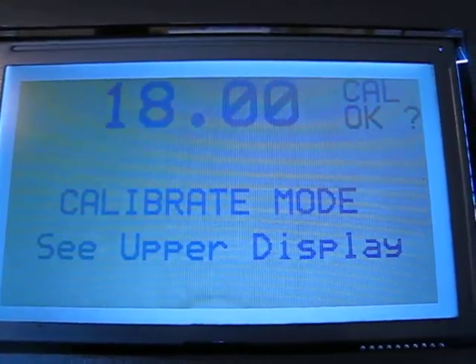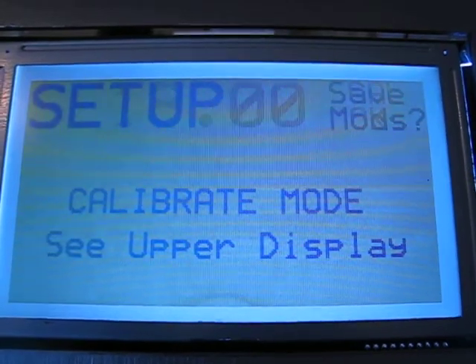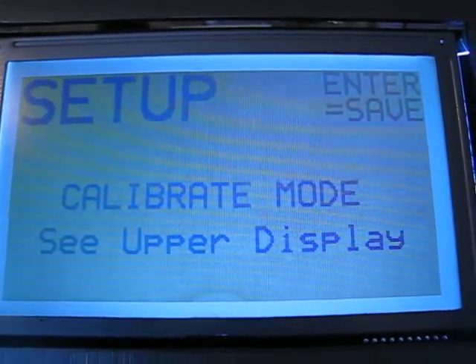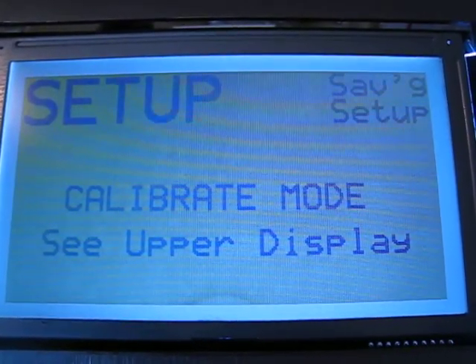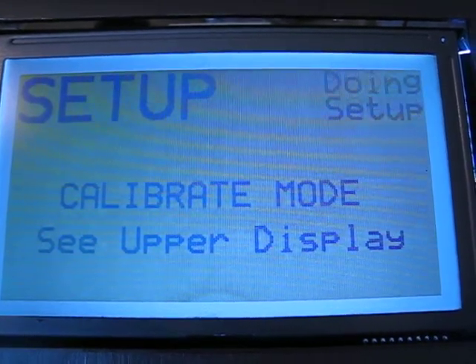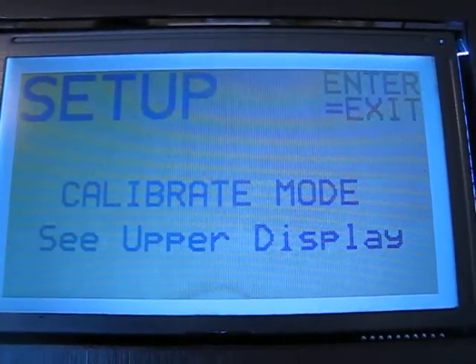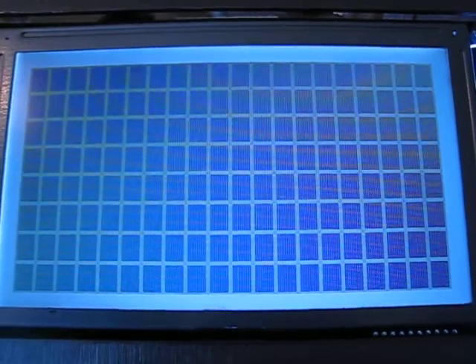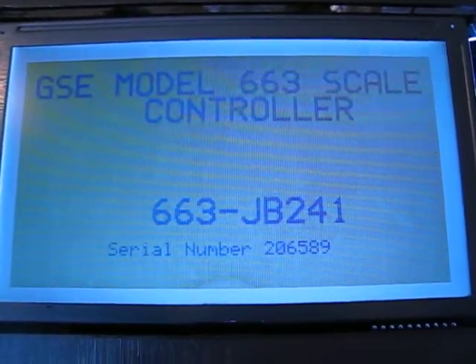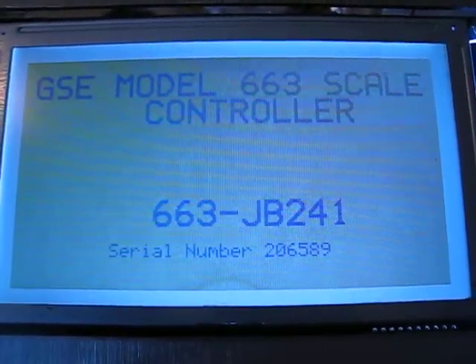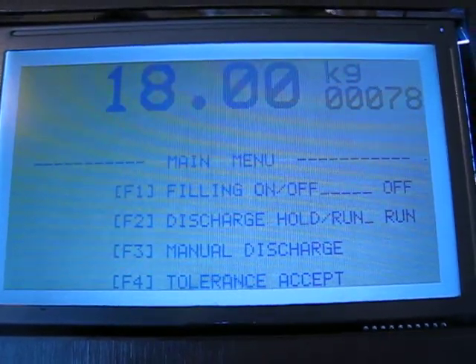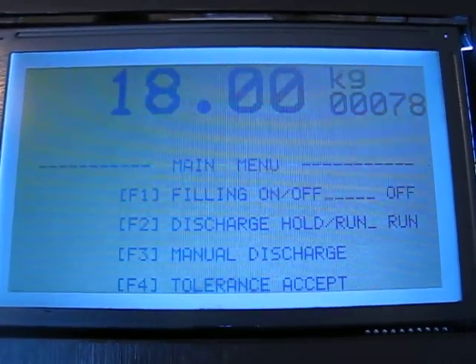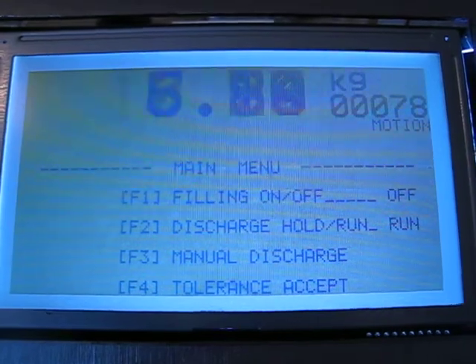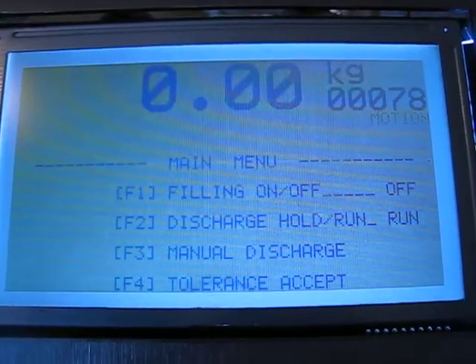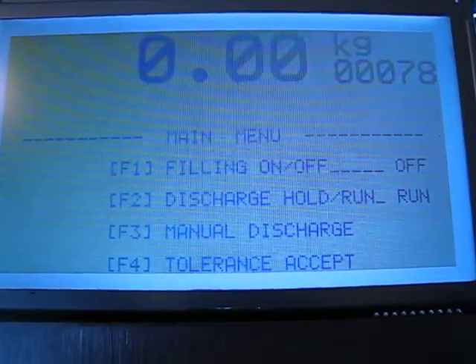Yeah, that looks good. Calibrate, OK. Enter. Enter to save. We'll save the calibration. And enter to exit. And now the calibration is complete. And if our weights are still hanging on the scale, when it reboots, we see that there's 18 kilos. And then we remove the weights off the scale and we see that's reading 0, so the calibration is good.